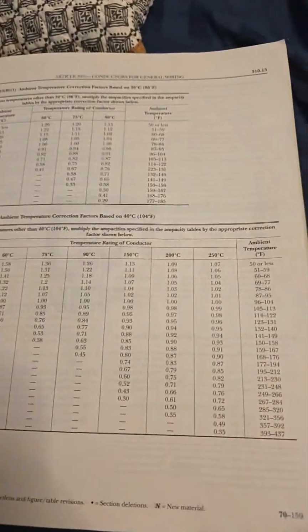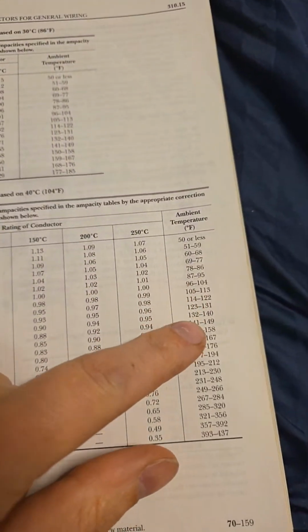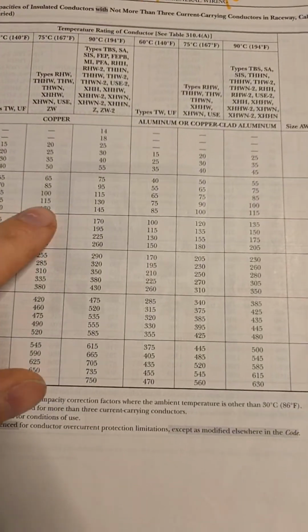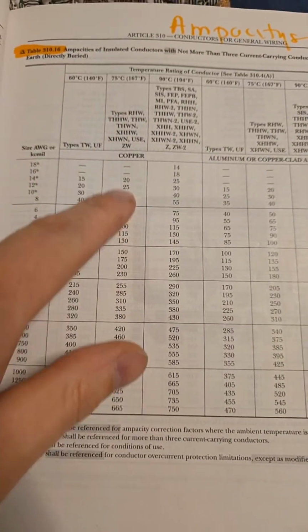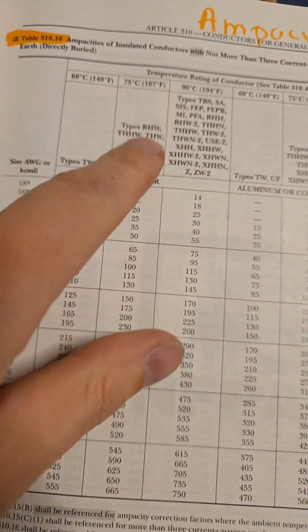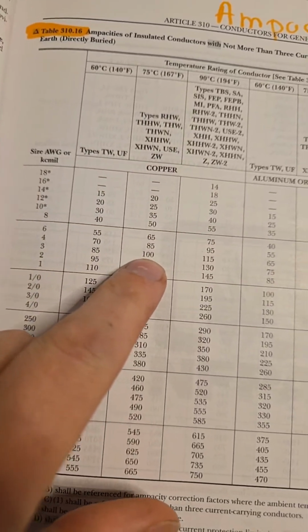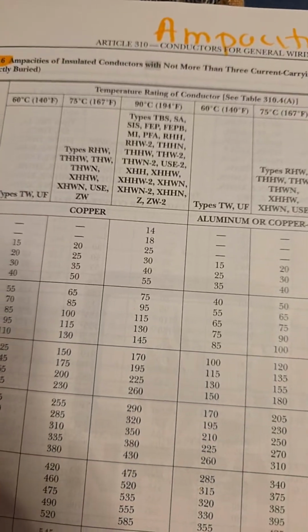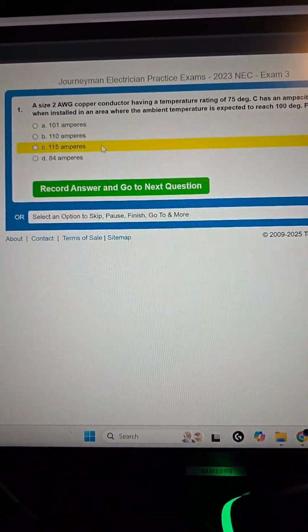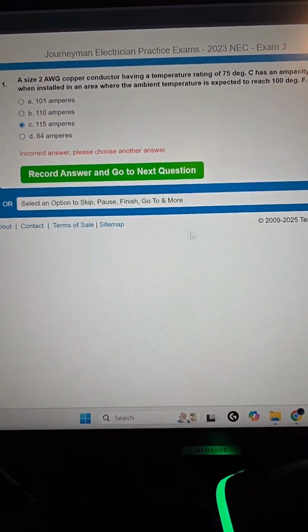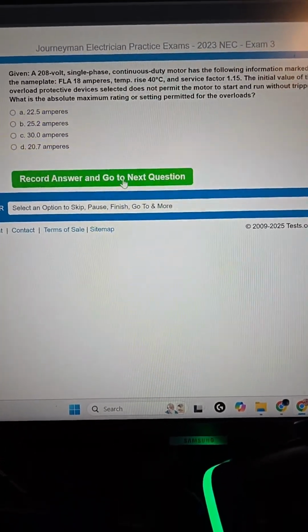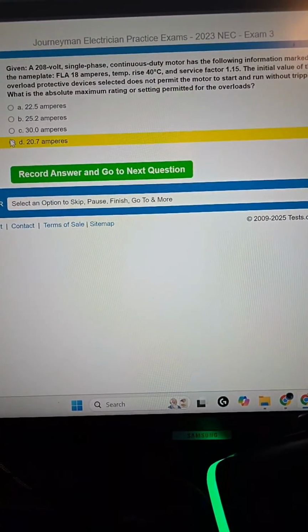But in general, what you're going to do is go here to 310. This is your ambient temperatures here. There's your multipliers. I'm not going to pull out the calculator. There's your ambient temperature in degrees. This is what we started at. So number 2 being good for 115 here on the 75 degrees C. There's a 167 degree Fahrenheit. So let's see here, 100. Number 2, 115 on the 75 degrees C. What is the question? I'm going to say it's 115. We got it wrong. Next. Okay, 208 volts. Okay, next question. Come on, next question.